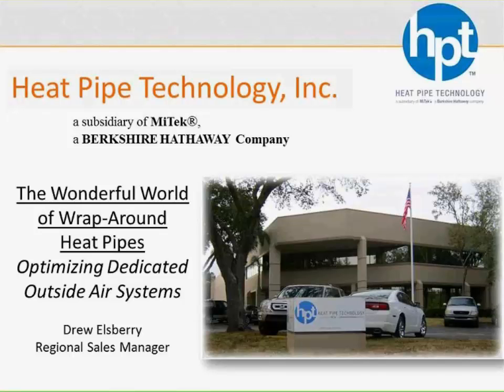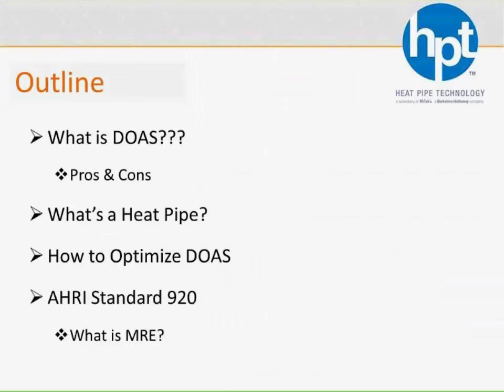So today we're going to get back into the wonderful world of heat pipes and not just focus on the wraparound heat pipe. Those who have been with us on earlier sessions, we focused on the heat recovery modules and then our DHPs, or our dehumidification or wraparound heat pipes. But today we're actually going to take it a step further and focus on dedicated outside air systems. Dedicated outside air systems, or DOAS as it's commonly referred, I'm going to just focus on what that actually is and discuss the pros and cons of that type of system versus your more conventional mixed air type system. And then of course, what's a heat pipe?